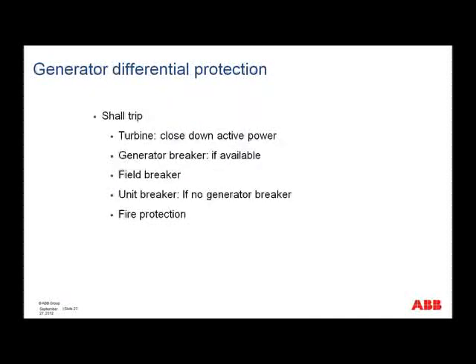So what should happen if the differential protection operates? Well, we need to close the turbine down. We need to take away the active power. We need to trip the generator breaker if it's available. We need to trip the field breaker. And if there's no generator breaker, of course, we then need to trip the HV side of the step-up transformer, the breaker there, and possibly also the fire protection.